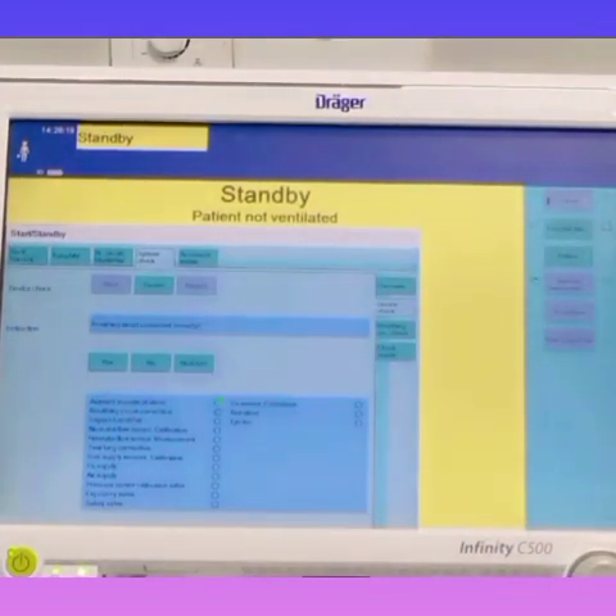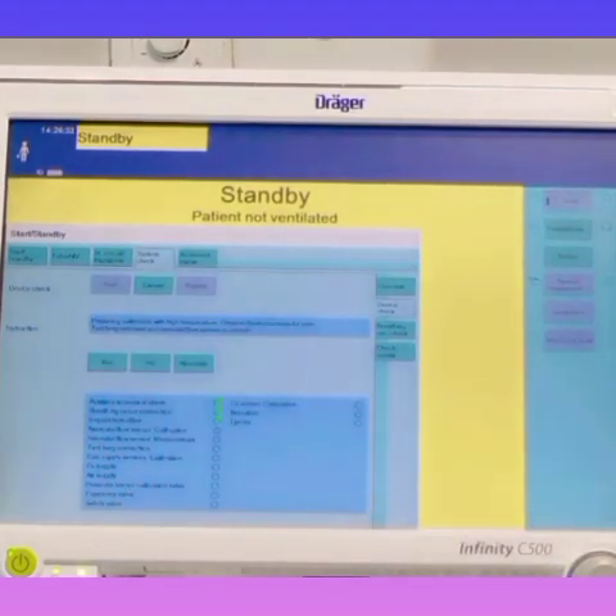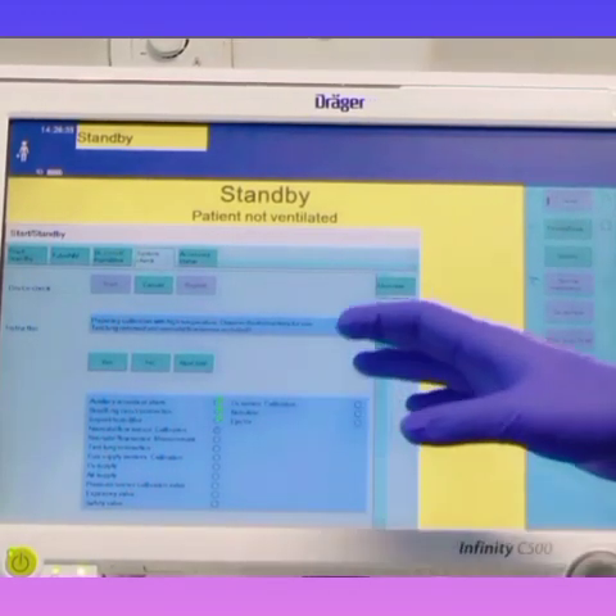So is alarm audible? Yes. Heated breathing circuit connected correctly? You have connected it correctly? Yes. Humidifier connected correctly or not used? Yes, it is connected correctly or not used. Preparing calibration with high temperature. Observe the instruction for use.